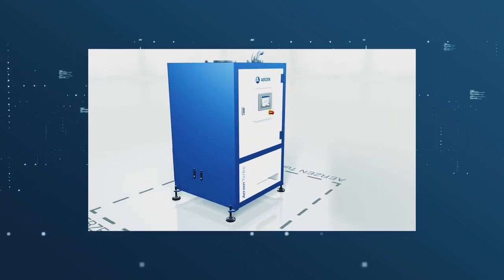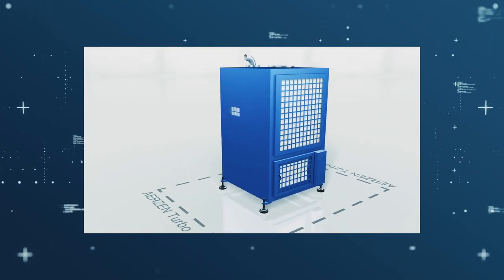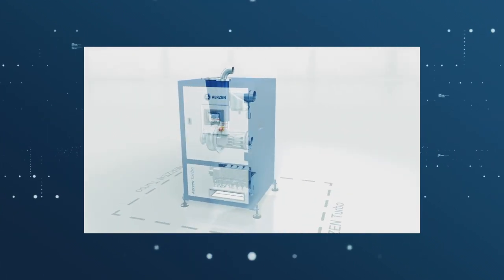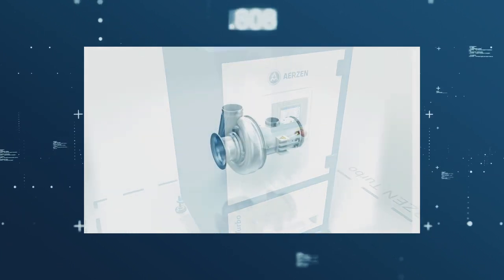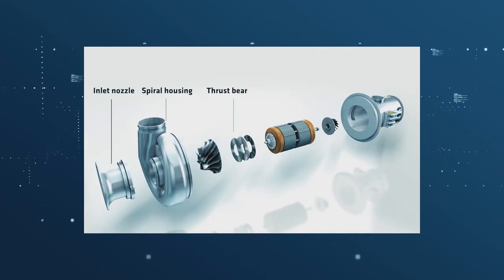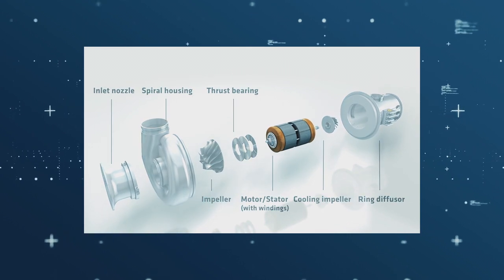The turbo blower is an innovative package blower system which offers a completely integrated design for a plug-and-play approach to provide variable flow and pressure points through reliable and energy-efficient operation. The turbo blower package contains a single-stage centrifugal compressor, which conveys low-pressure compressed air by a radial impeller directly coupled to a high-speed motor, allowing the elimination of any transmission losses.